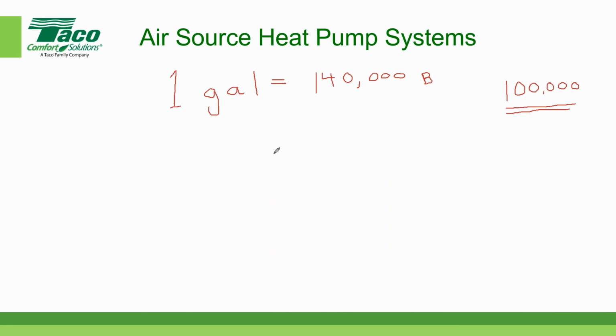140,000? Again, this is a residential system, so we're going to use very, very simple numbers here. If I have a gallon of fuel, I can only get roughly 80%. I know that boilers are a little bit more efficient, but for simple math tonight, we're going to say 140,000 times 0.8. So that means that 1 gallon has 112,000 BTUs of heating capacity at 80% efficiency.